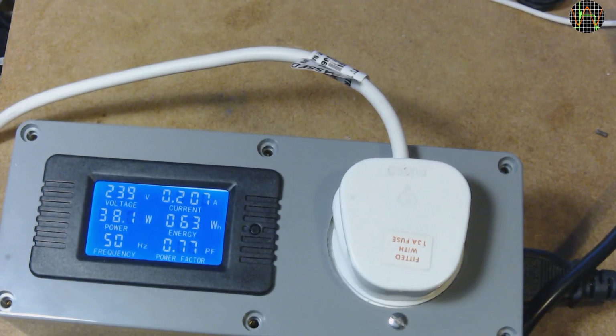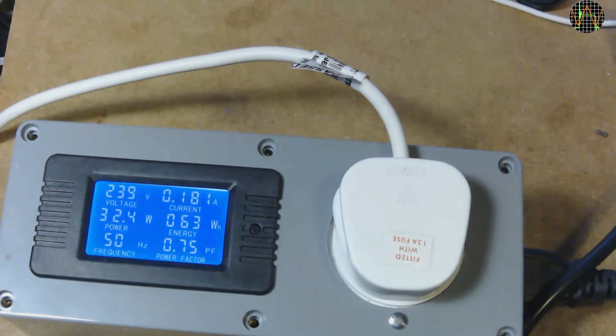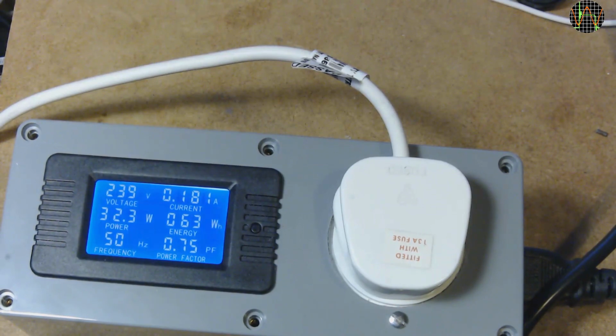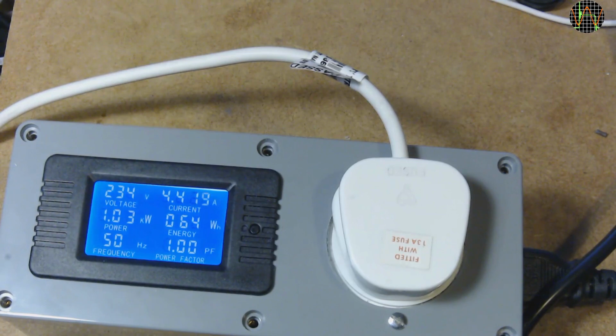For a first test, I plugged in a fan heater. At first only the fan is running, which draws 180 milliamps and uses about 33 watts and has a power factor of 0.74. When I turn on the heater, the current jumps to 4.4 amps and consumed power is now 1 kilowatt plus the power of the motor.